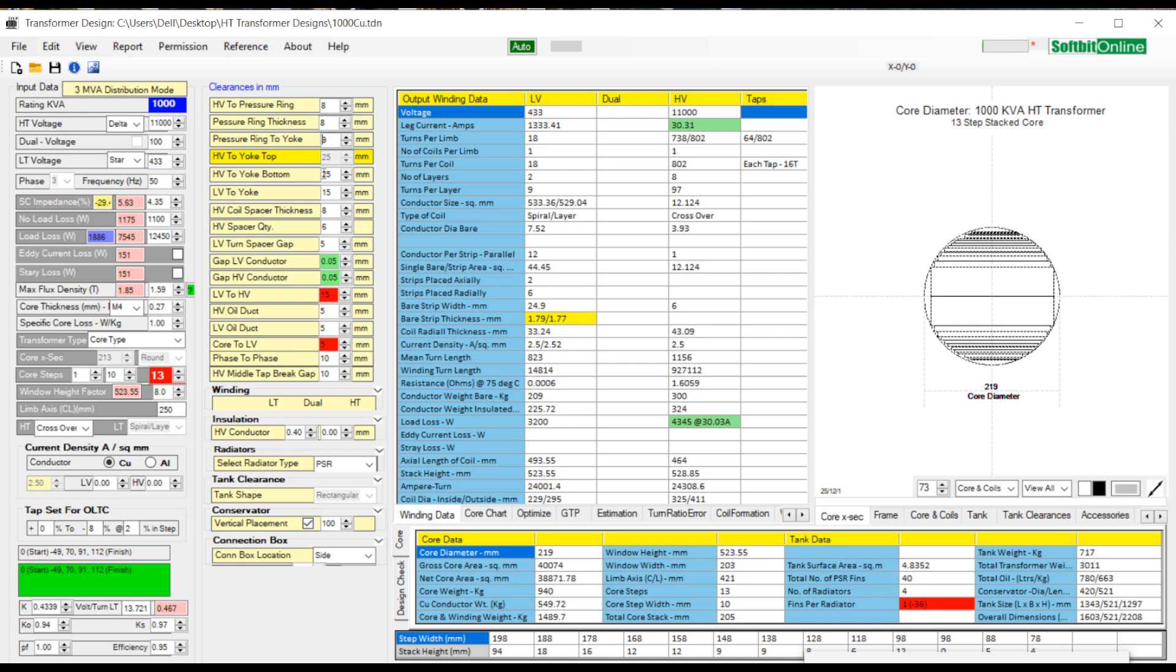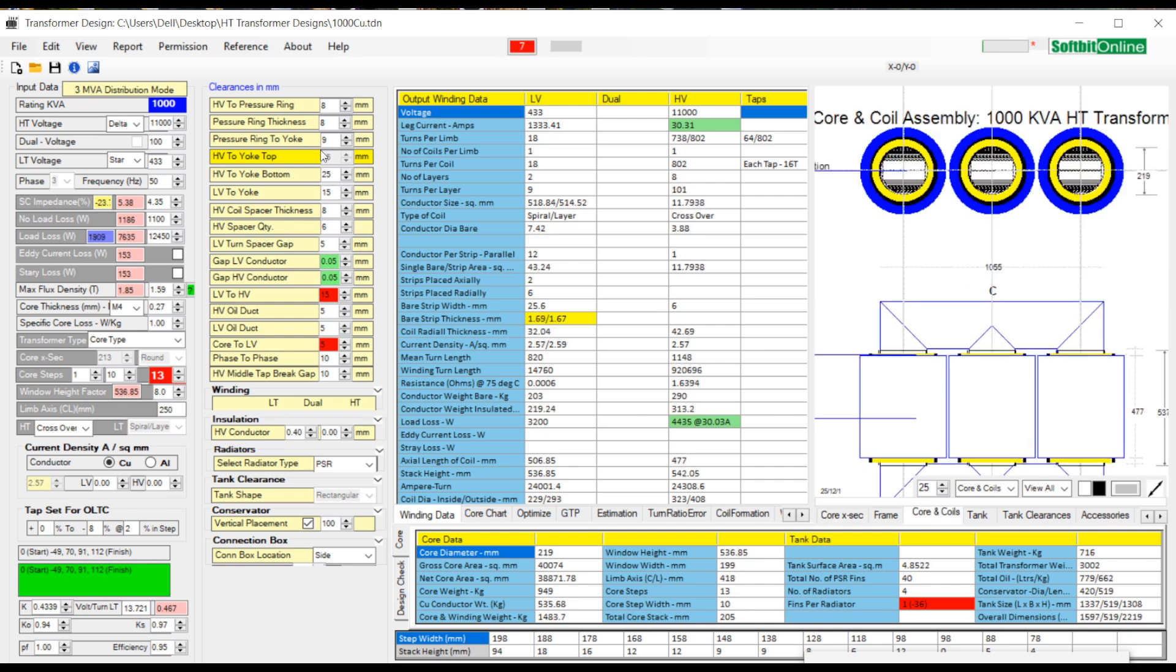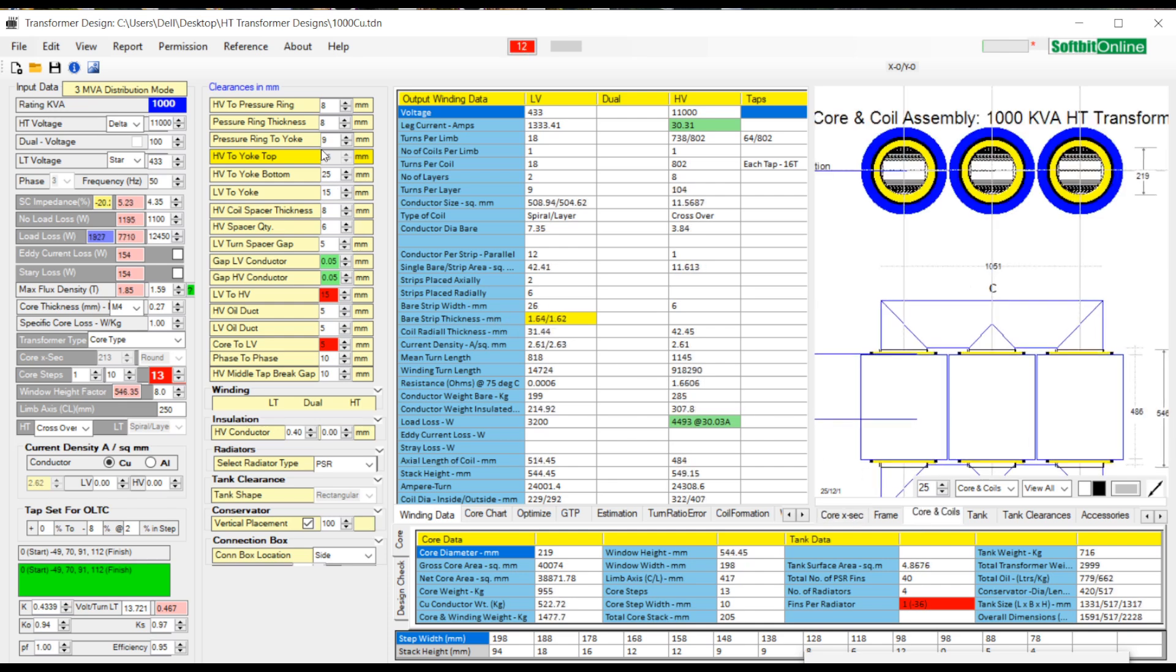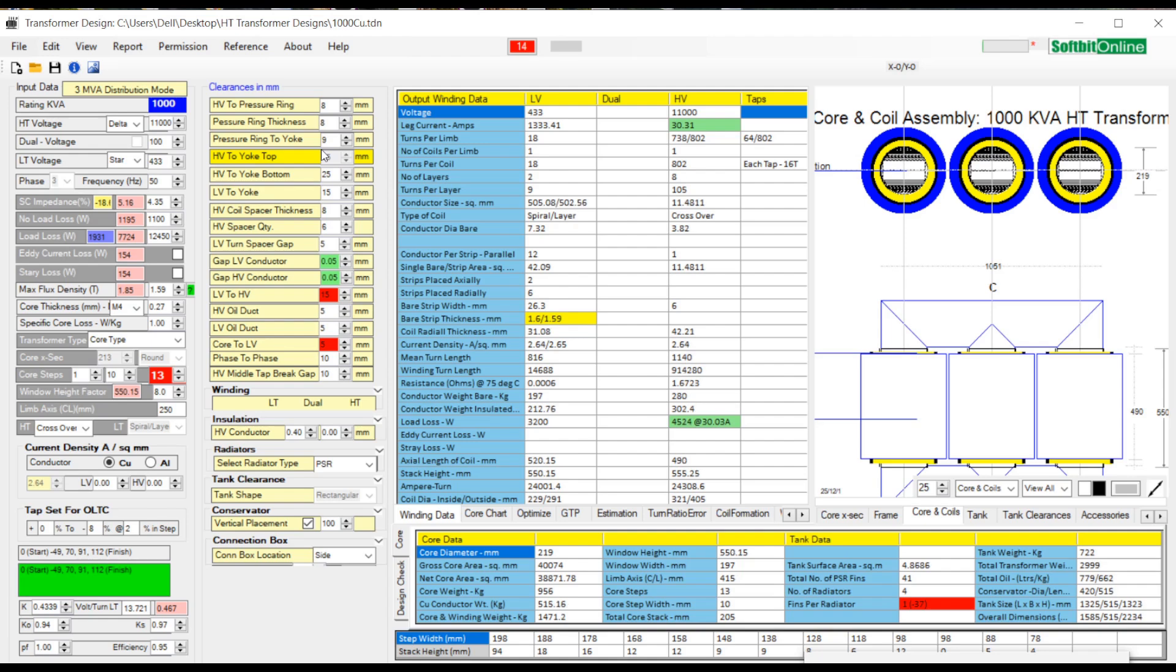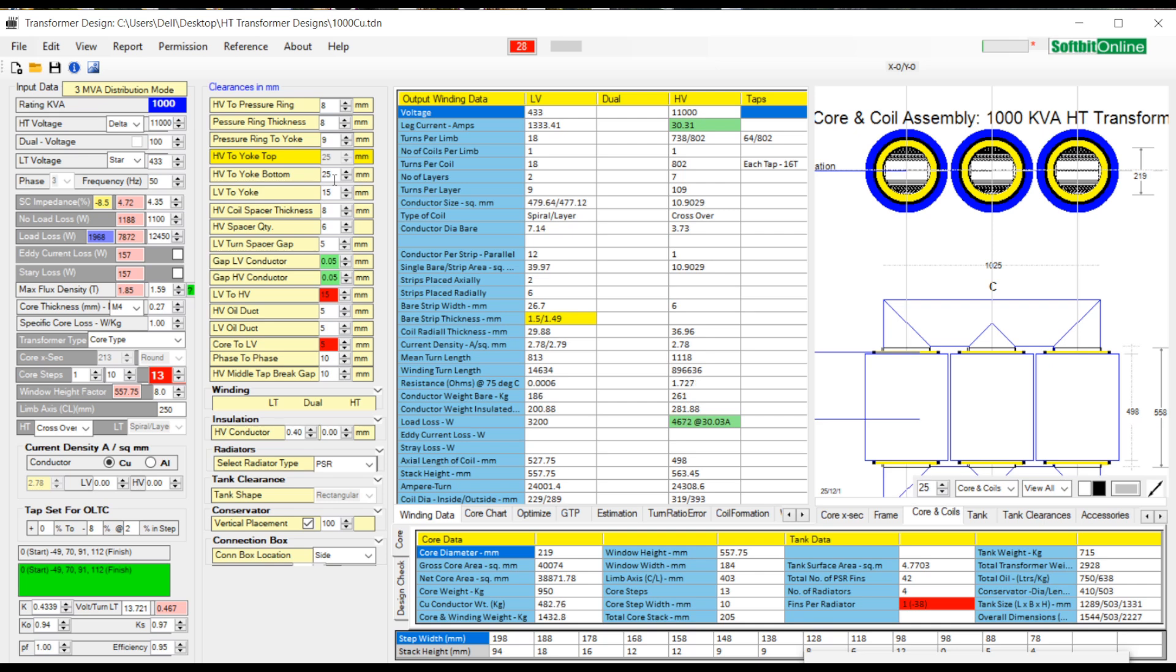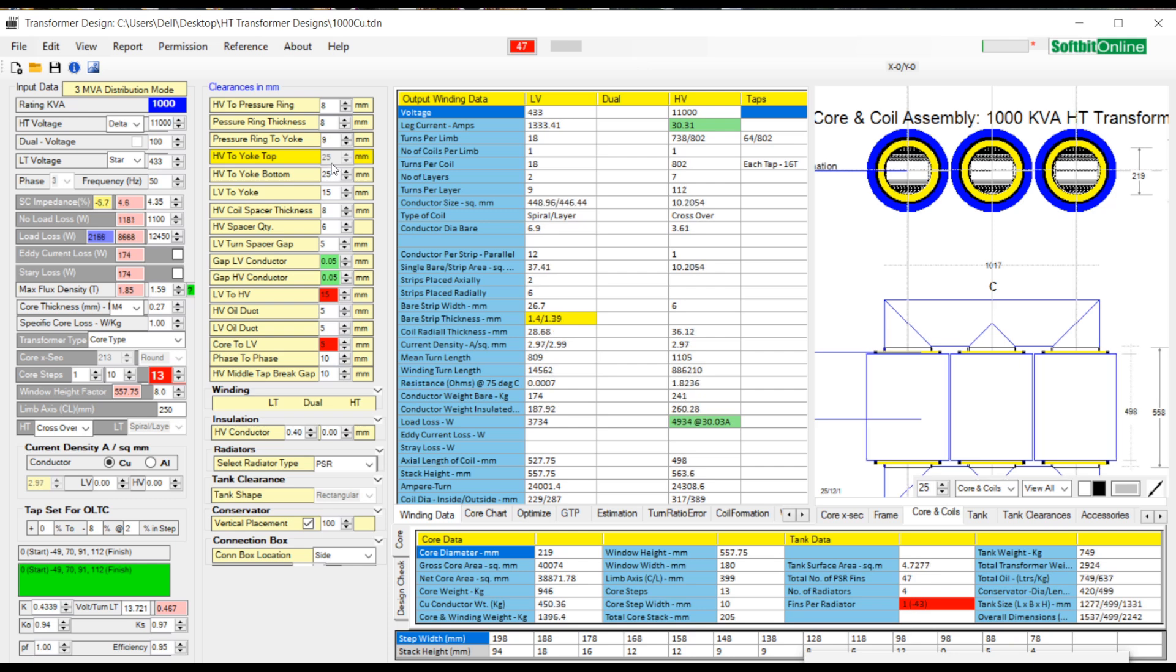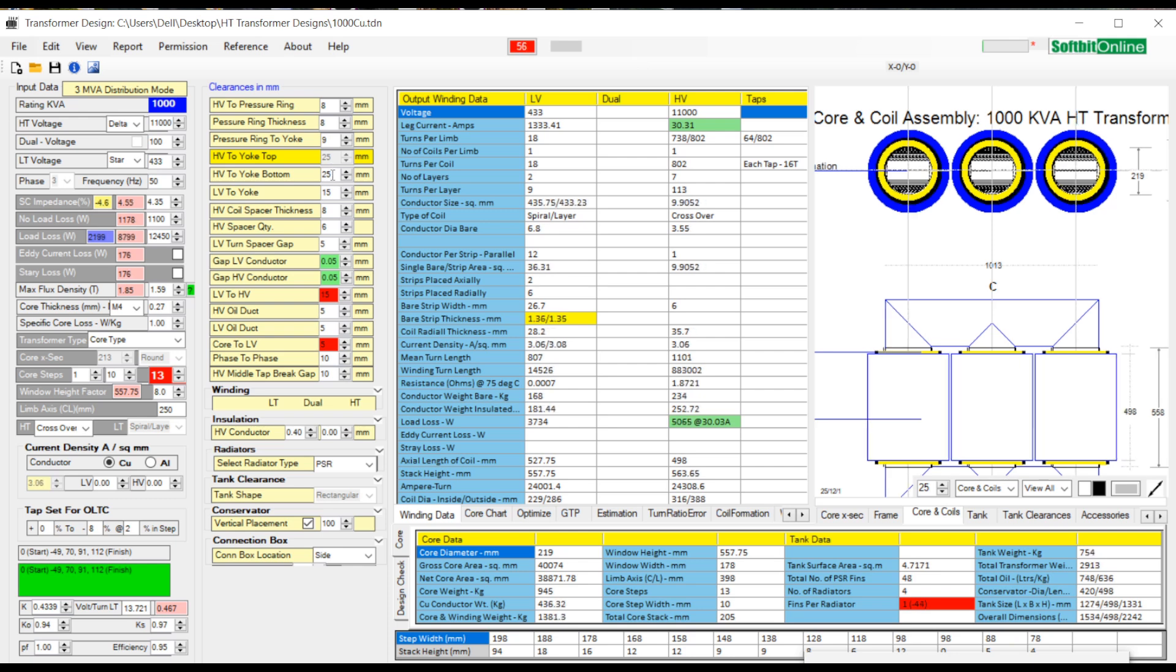Very first gap is from top of HV winding to pressure ring in mm. Then we enter thickness of pressure ring, and clearance from pressure ring to top yoke. The sum of these 3 values is the 4th value which is HV to yoke top. In smaller rating transformers the thickness of pressure ring can be put 0 and other 2 values can be added, and sum of these 2 values would be the HV to yoke top.